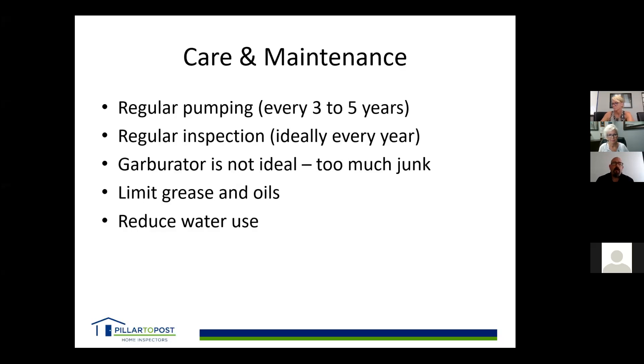There are some maintenance items: regular pumping is one, and regular inspection ideally every year — take the lids off and look inside. Most people won't do that, but it's a good idea. Also, do not use a garburator — garburators put more solids into the tank than necessary. Grinding up vegetables and meat and sending it in causes the tank to need pumping sooner, and it's not designed to take that raw material.